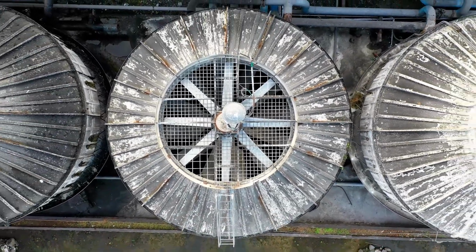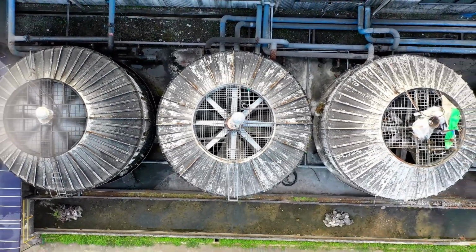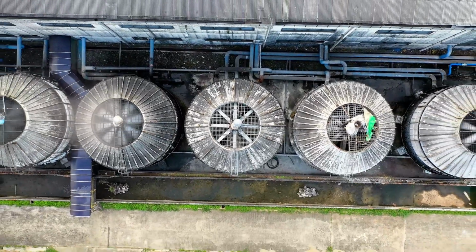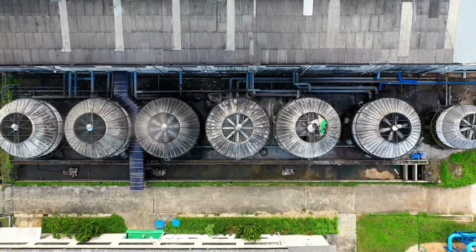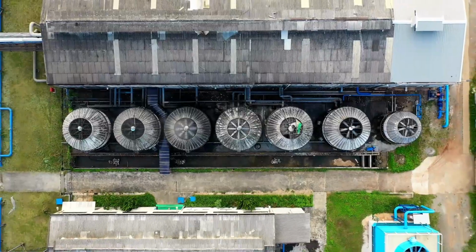External static pressure, ESP calculation. External static pressure is the measurement of all the resistance in the duct system that the fan has to work against. Examples are filters, grills, AC coils, and the ductwork. It is the sum of the suction pressure and discharge pressure created by the equipment blower.